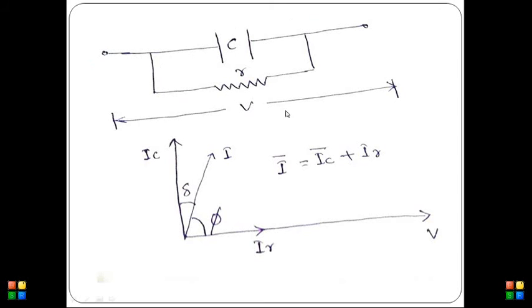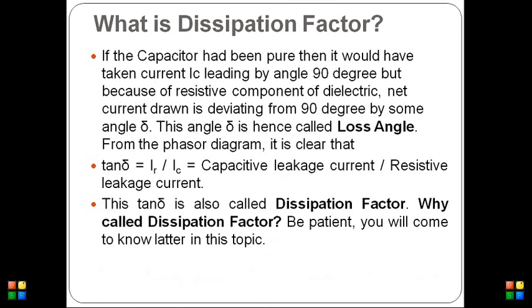I have applied a voltage V across the terminals of the capacitor and drawn the phasor diagram of this circuit. IC is the capacitive leakage current, IR is the resistive leakage current, and the net current is the vector sum of IC and IR. This net current I makes an angle delta with IC. Calculating tan delta: tan delta equals IR divided by IC, that is resistive leakage current divided by capacitive leakage current. This tan delta is called the dissipation factor and the angle delta is called the loss angle.